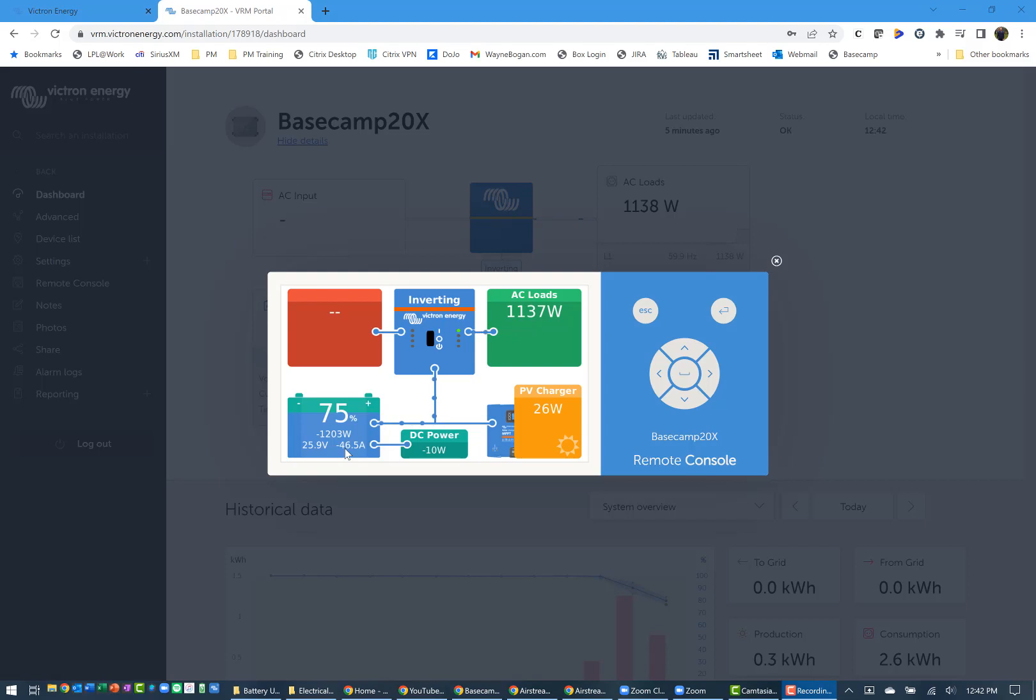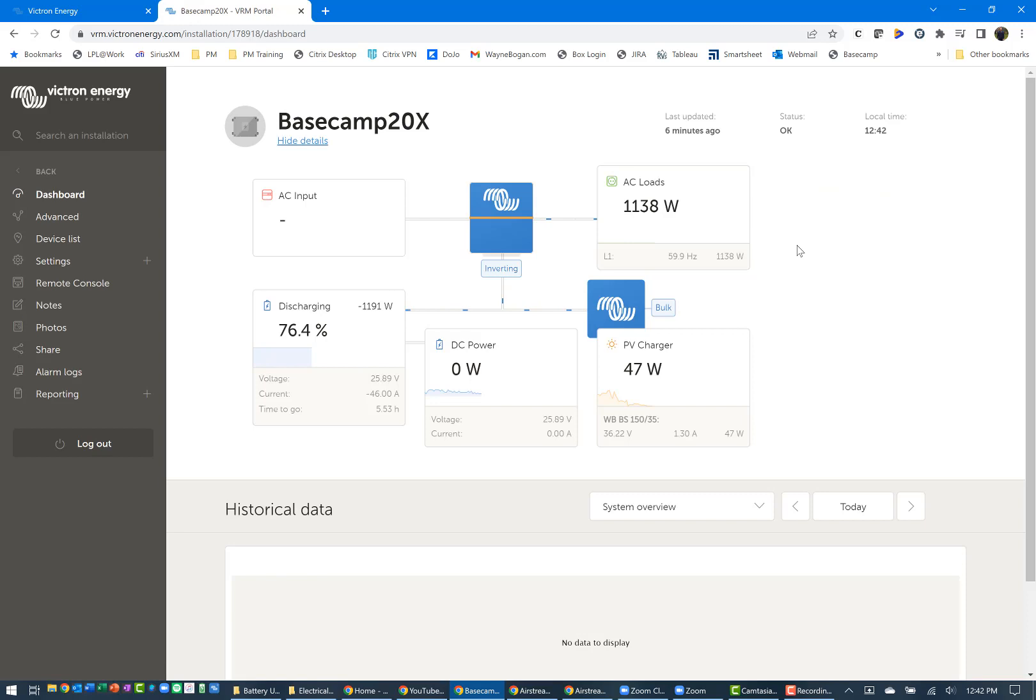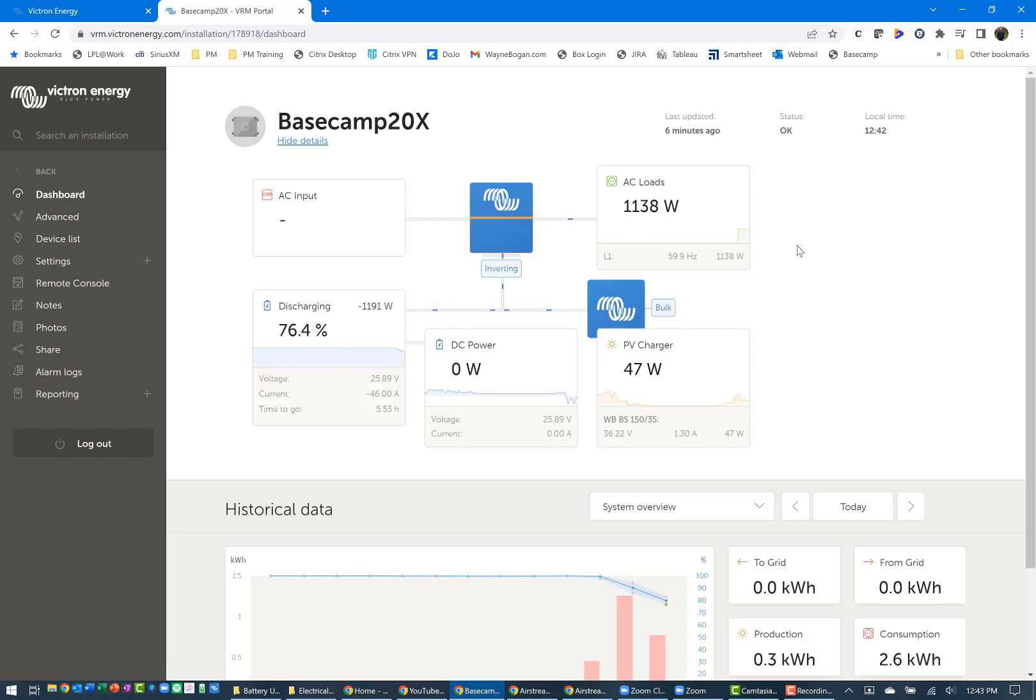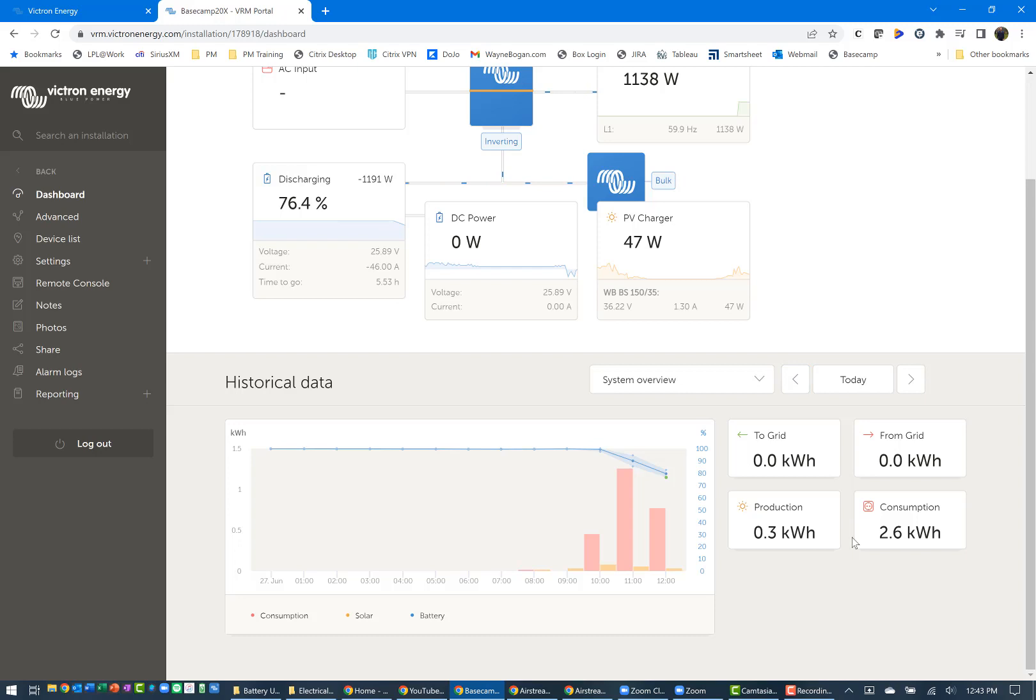Part of that's been offset, I think, by how much is coming in from the solar on the PV charger side. Let's look at the historical data. It's a little bit behind what's happening in real time, but if I come in and hit refresh on the screen, you can see in the portal from Victron that it's pretty close on the load where we are with the batteries. It gives you a little additional detail such as you can look at the voltage, you can see the current showing at 46 amps, and then showing an estimated five to six hours after our two hours of running.